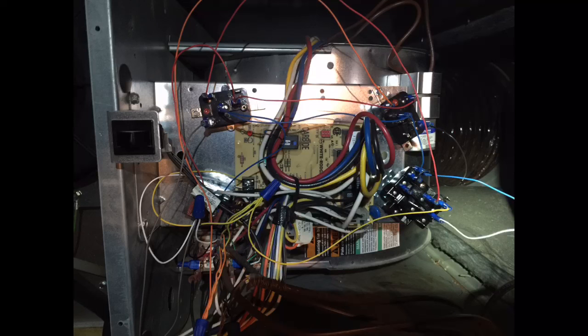So in this instance, I've got a 9293 on the upper right above the circuit board. I've got a 9380 below it, and then over on the left I've got another 9293. The 9293 takes power and allows the system to energize when the gas furnace comes on. The 9293 on the upper right is for the heat pump, and then the 9380 on the bottom right is the relay for the Y terminal. And earlier I said it was for the heat pump. That's actually, the one on the upper right is for the O terminal, or the reversing valve.